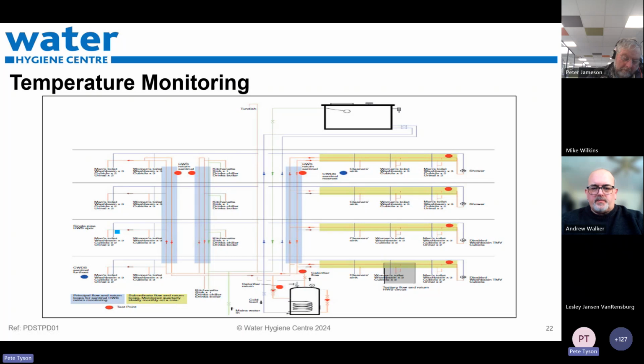The return loops are the hidden elements of the system which traditionally have not been measured or checked. Although the 2014 revision of HSG 274 Part 2 and the 2016 revision of HTM 04-01 Part B require identifying these loops and how best to take temperatures, whether manually, via monitoring connections, BMS, or other remote monitoring systems. One consideration for which kit we use is accessibility, cost, time, and effectiveness.